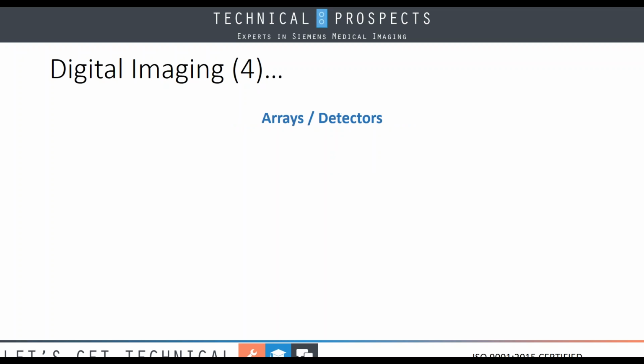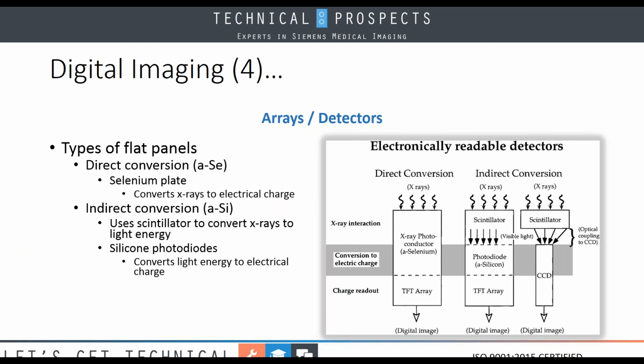Moving on from CR, let's take a look at some arrays and detectors. Here, we're looking at various types of flat panels. When you look at the direct conversion, shown in the picture, you see it uses a selenium plate, and here the X-rays are converted directly to an electrical charge through the selenium. When we use the indirect conversion, to the right of the direct conversion, you have two different types. One uses a scintillator, which will convert the X-ray to light energy and will go through photodiodes and then charge our transistors, or we'll send it from the scintillator directly to a CCD camera.